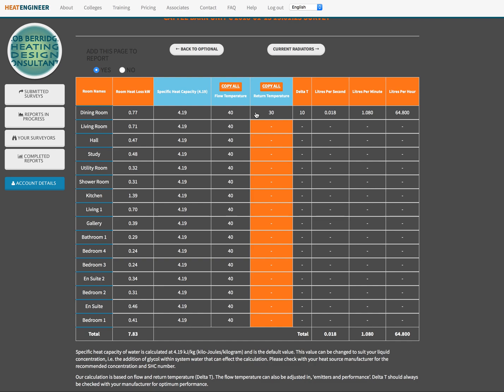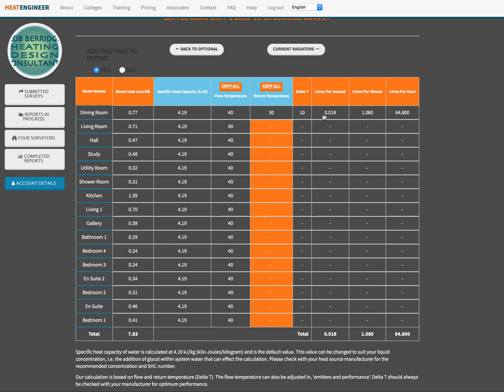Once you've filled those three in it populates the rest that we've got here. Now you can see what it's done for that dining room, that is basically 770 watts, so 0.7, nearly 0.8 kilowatts within that property with a specific heat of 4.19, 40 degree flow temperature, 30 degree return temperature, so a delta T of 10, is giving us 0.018 liters per second that we need to run through to maintain that, one liter pretty much per minute and 64, nearly 65 liters per hour.